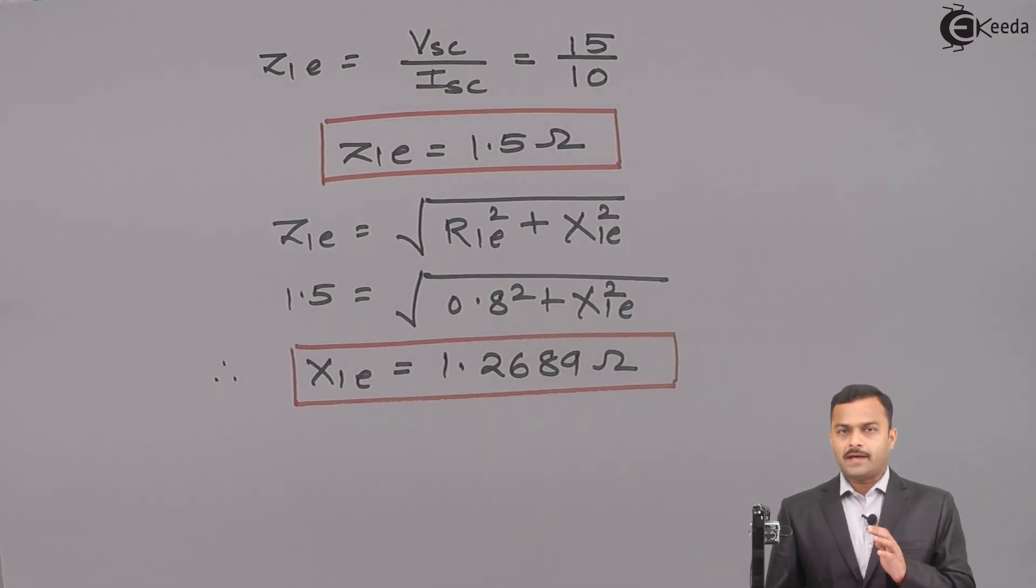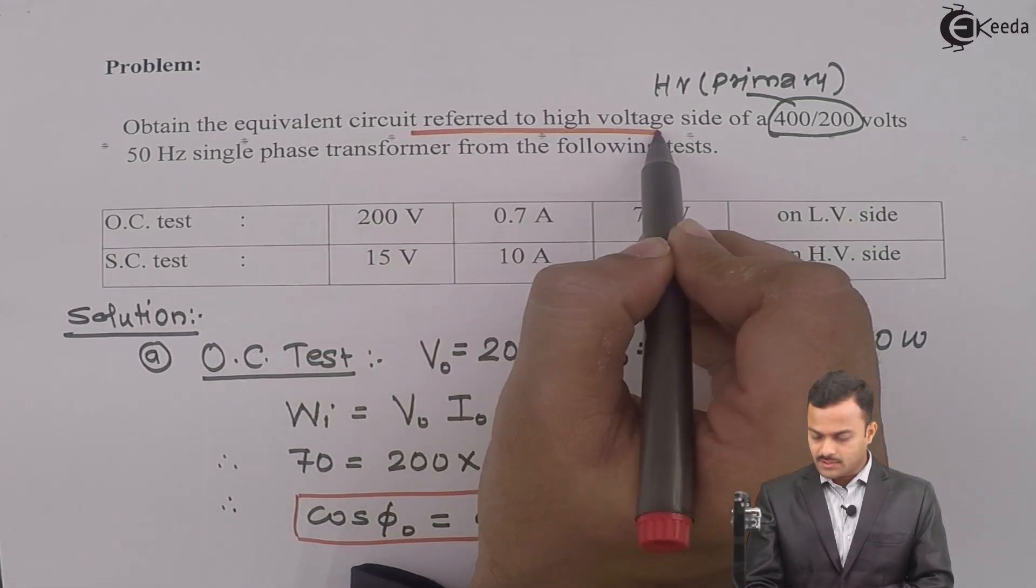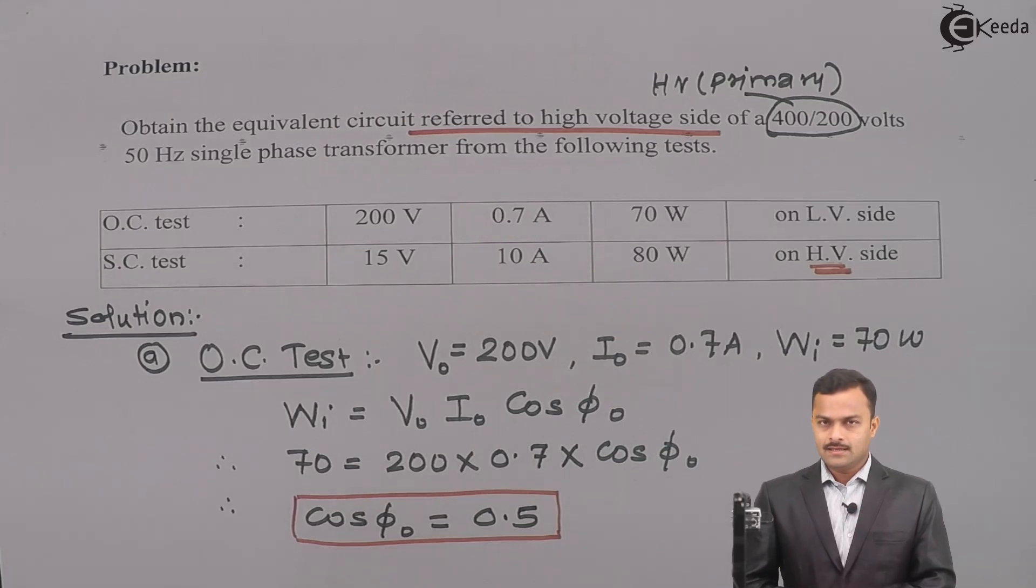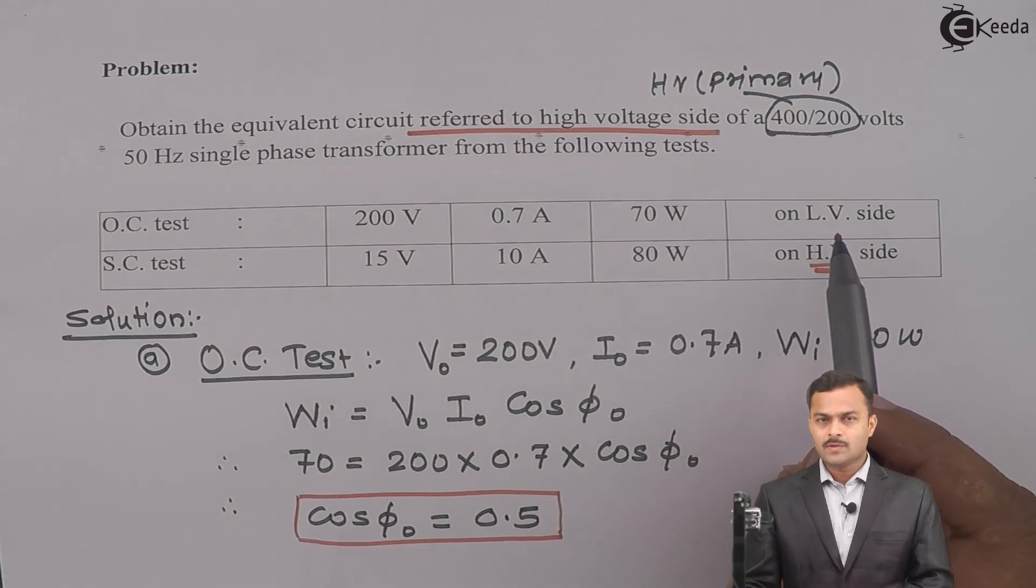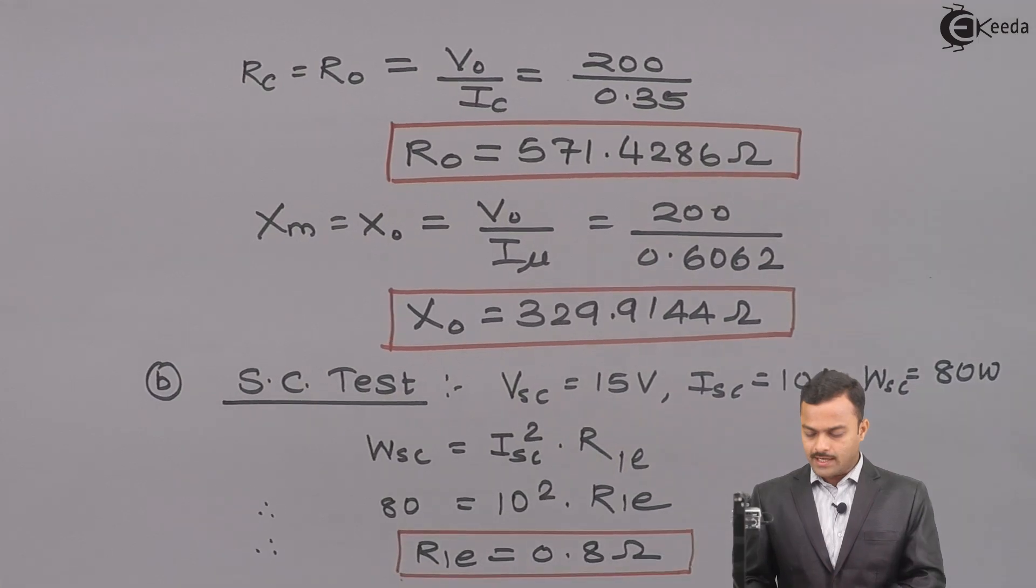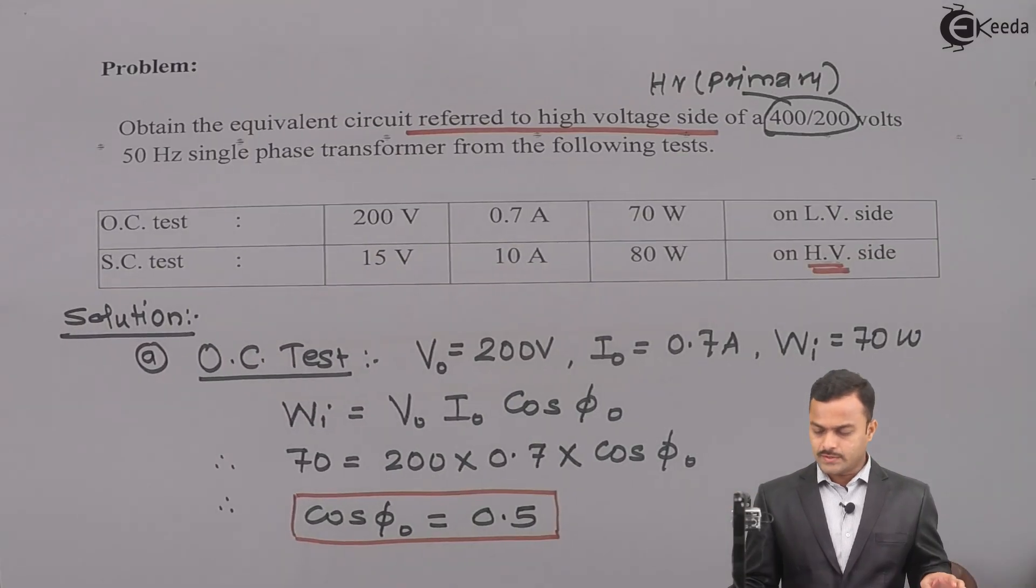Now, thing is that we are getting four parameters. Two from open circuit test and two from short circuit test. But what happened if you see the problem carefully, open circuit test is performed on low voltage side and short circuit test is performed on high voltage side. And what they have asked, obtain the equivalent circuit referred to high voltage side. So thing is that whichever test we perform on high voltage side, those parameters will remain as it is. But suppose we have performed another test with some different side. For example, here, OC test we perform on low voltage side. So we need to refer that side parameters to the HV side. Here, through OC test, we got R0 and X0 like this. But that is at the low voltage side. We want equivalent circuit at the high voltage side. So we need to refer this R0 and X0 on HV side.